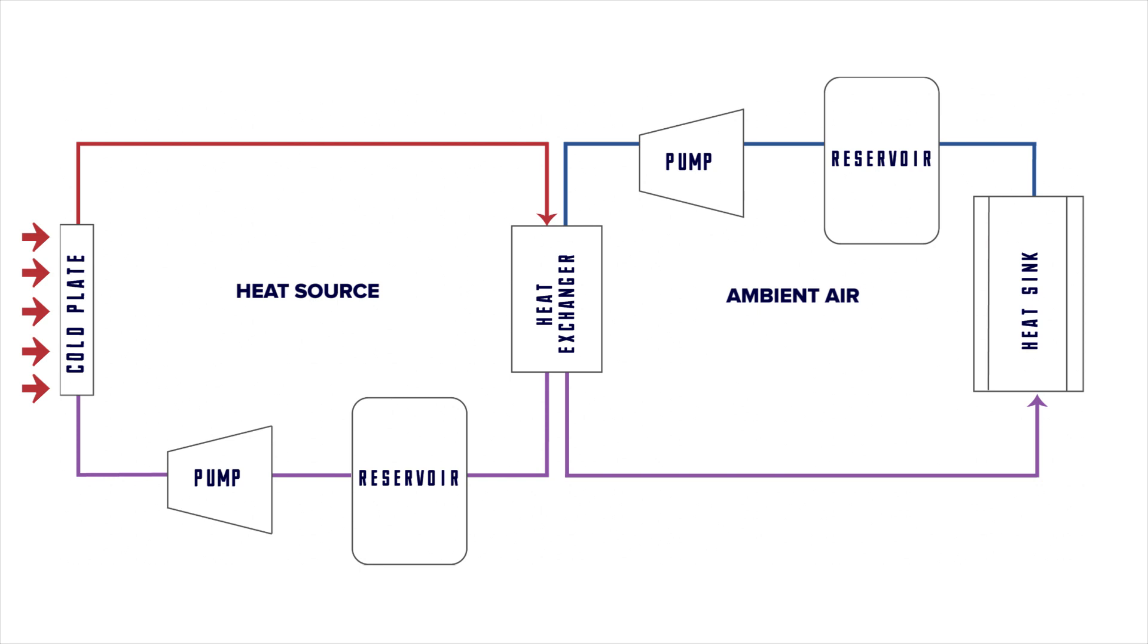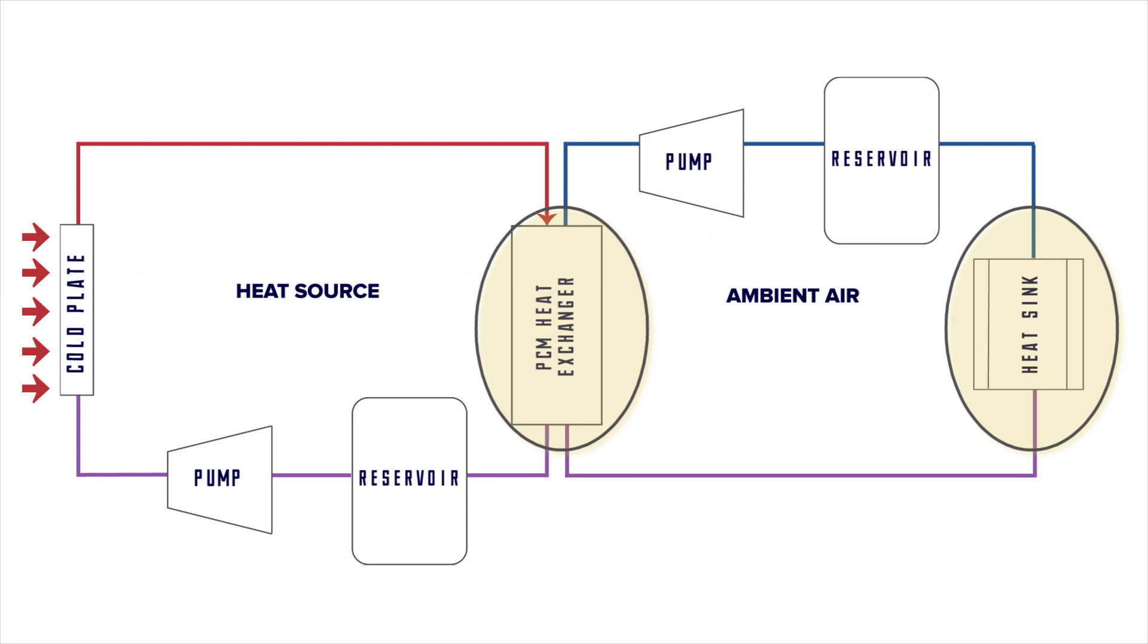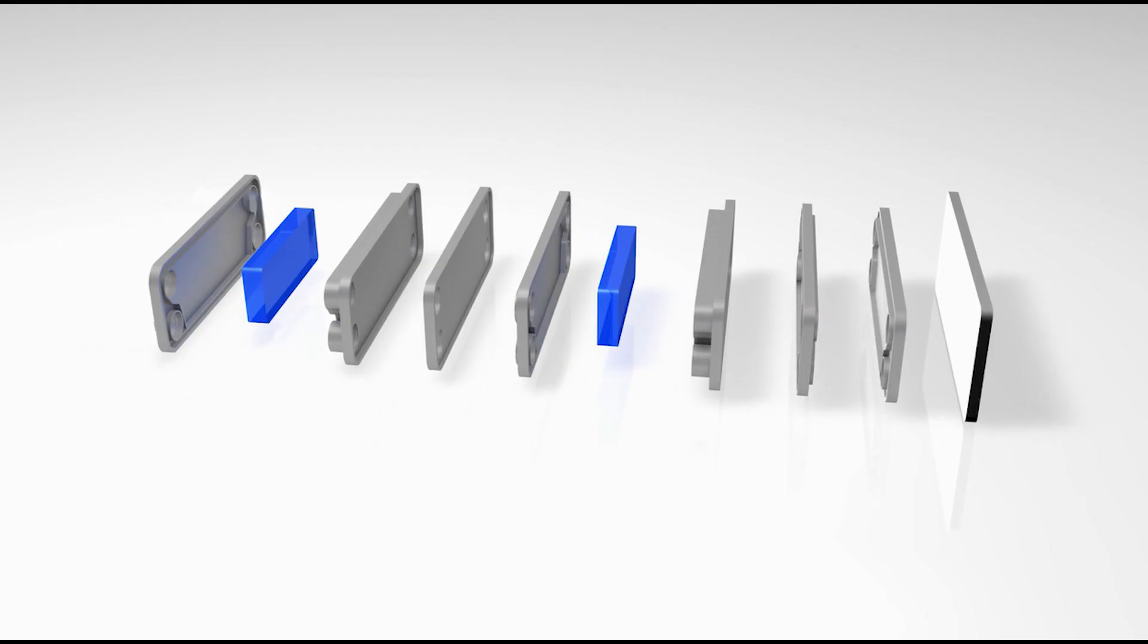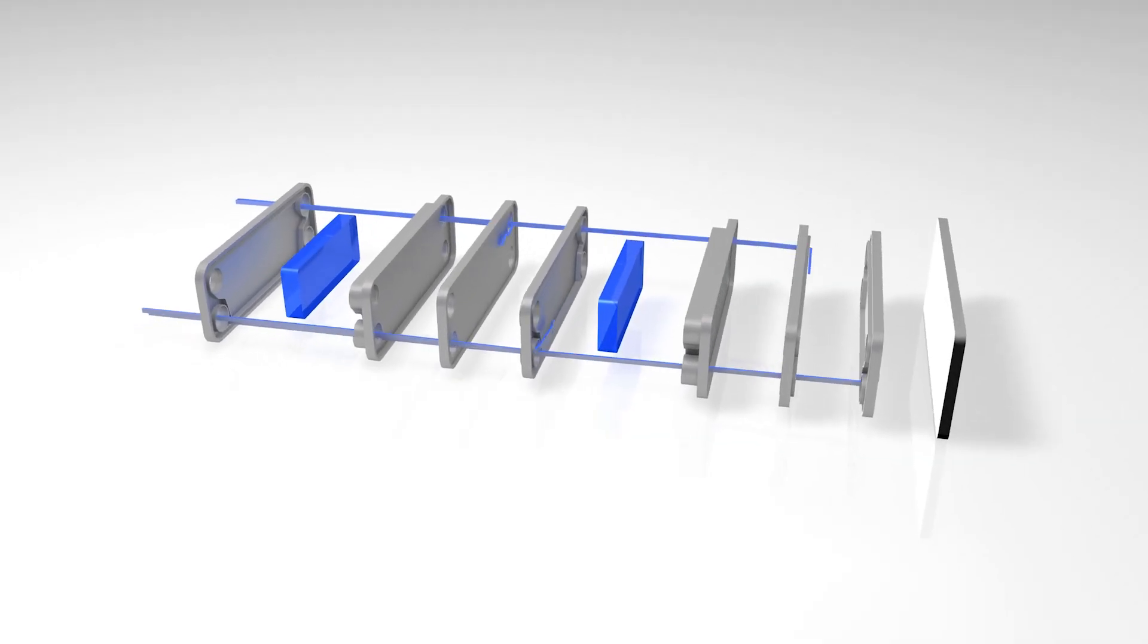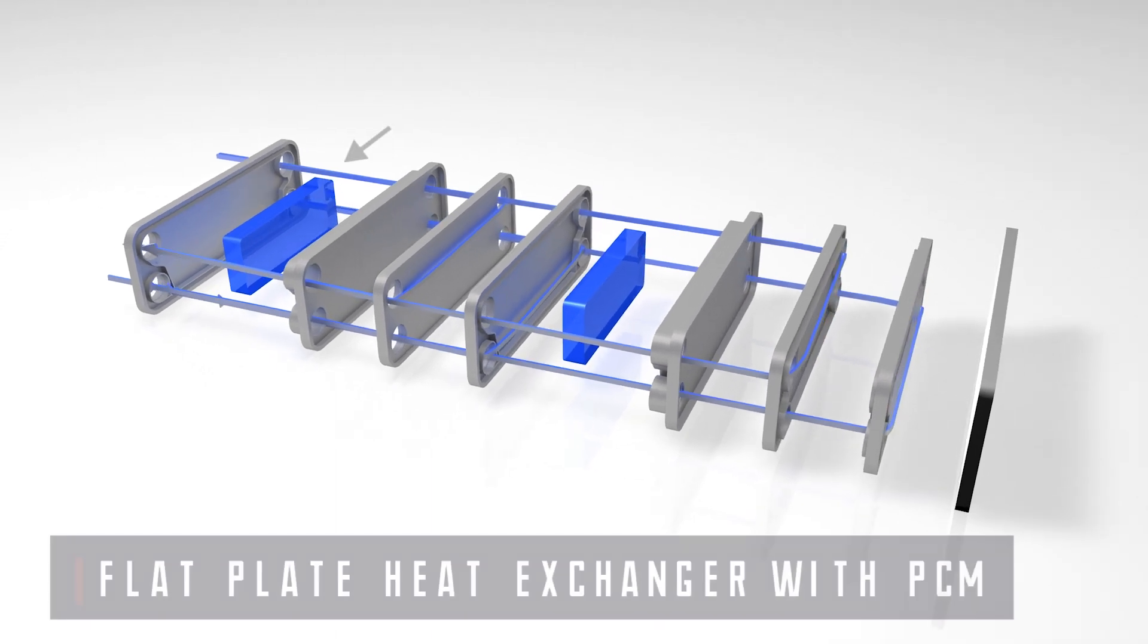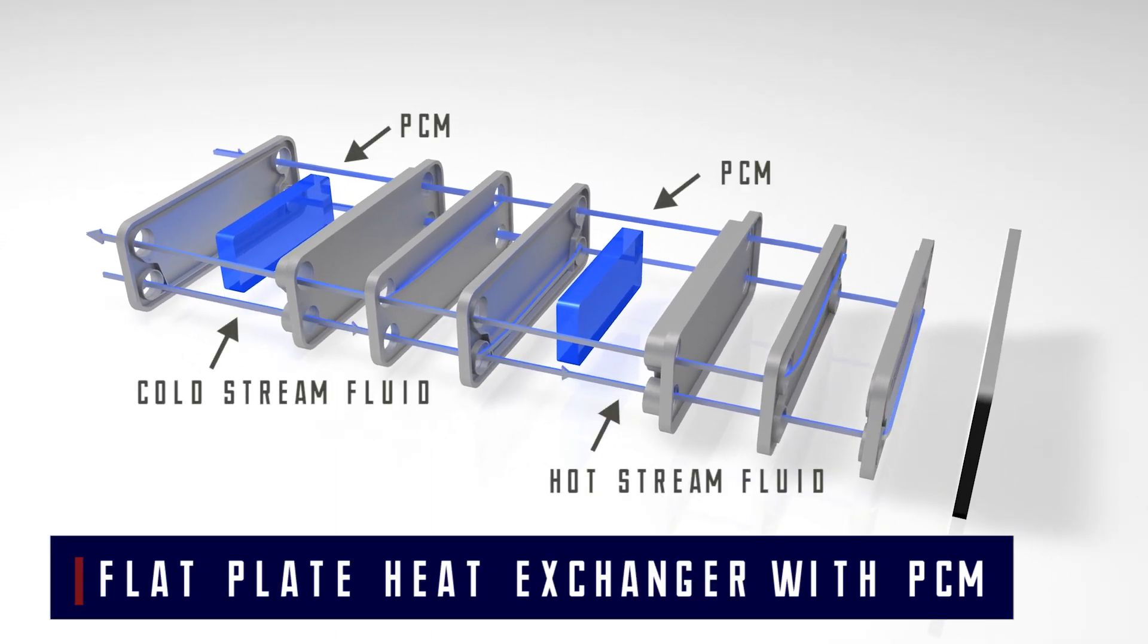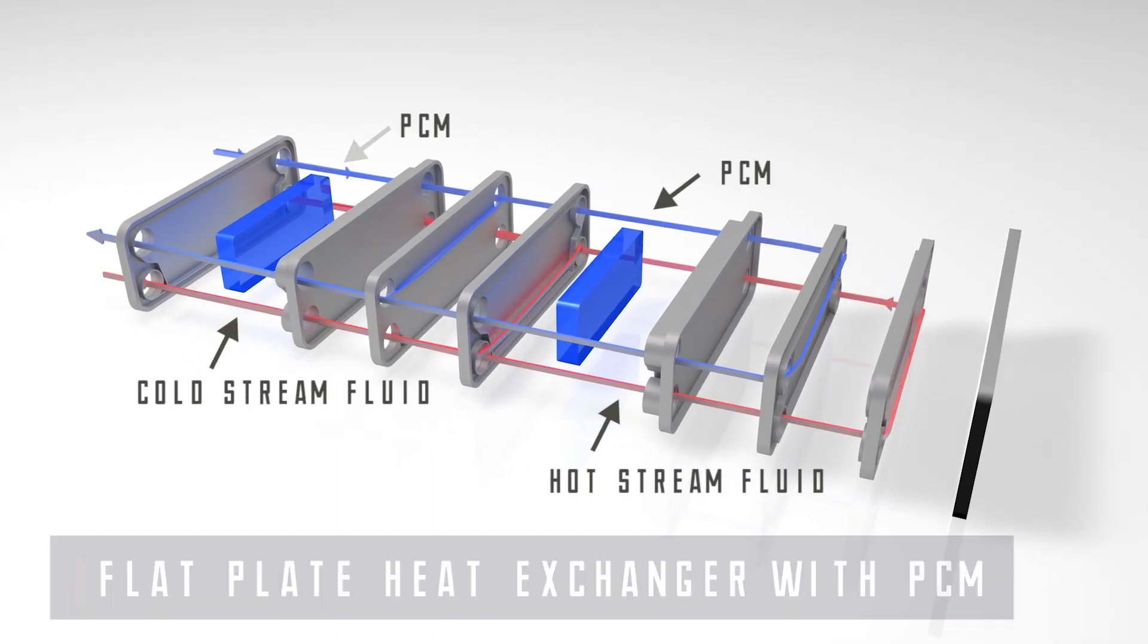In applications where the heat load is non-continuous, you can utilize PCM to dampen the heat load. The PCM achieves this goal by melting during the on portion and refreezing during the off period. This example shows an exploded view of a flat plate heat exchanger with PCM shown in between the hot and cold fluid streams.